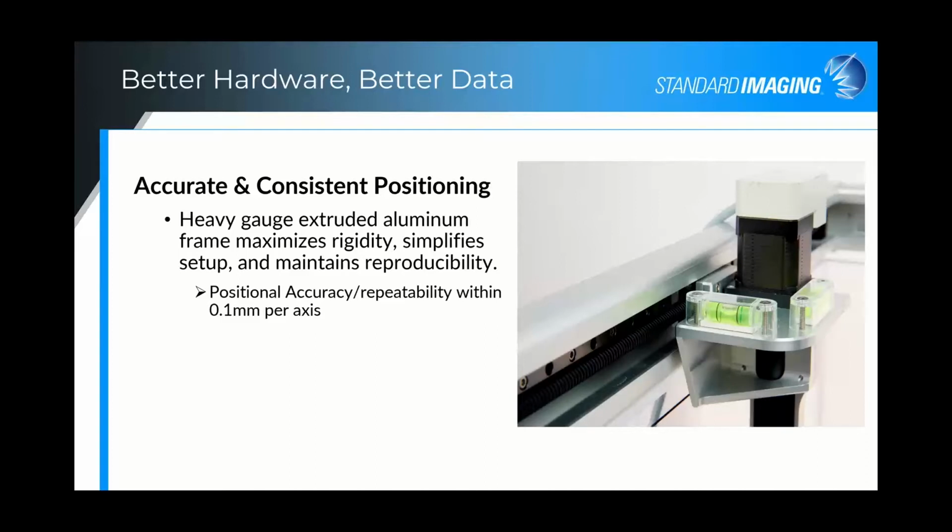We utilize redundant motors, so you won't have any cantilevering or skewing of the robot arms as it scans through the water. They maintain their positions because there are multiple motors doing the job. It allows for a precise and quick 3-point leveling, very quick and easy to do.